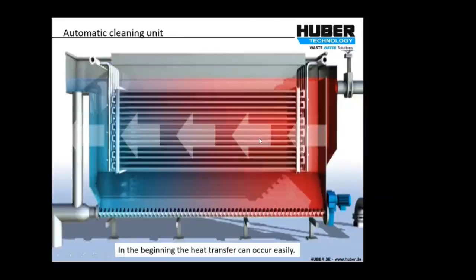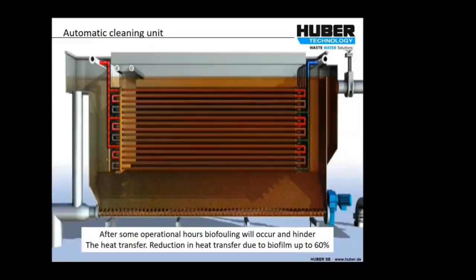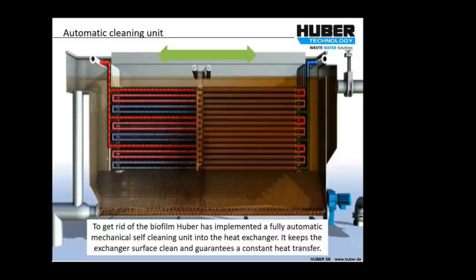So you can see there it's a tubular heat exchanger. The water to be heated up flows through these tubes against the flow of the incoming sewage, which starts off at nominally 14 degrees centigrade and goes out at about 11. After a while, as you can imagine, these things are sitting in sewage. You get biofouling. That is the primary cause of a heat exchanger suffering from performance inefficiencies in a sewage works, and it can actually reduce heat transfer efficiency by 60%. So what we have is an automated cleaning system to keep those tubes clean, to bring back the efficiency of the tubular heat exchanger.